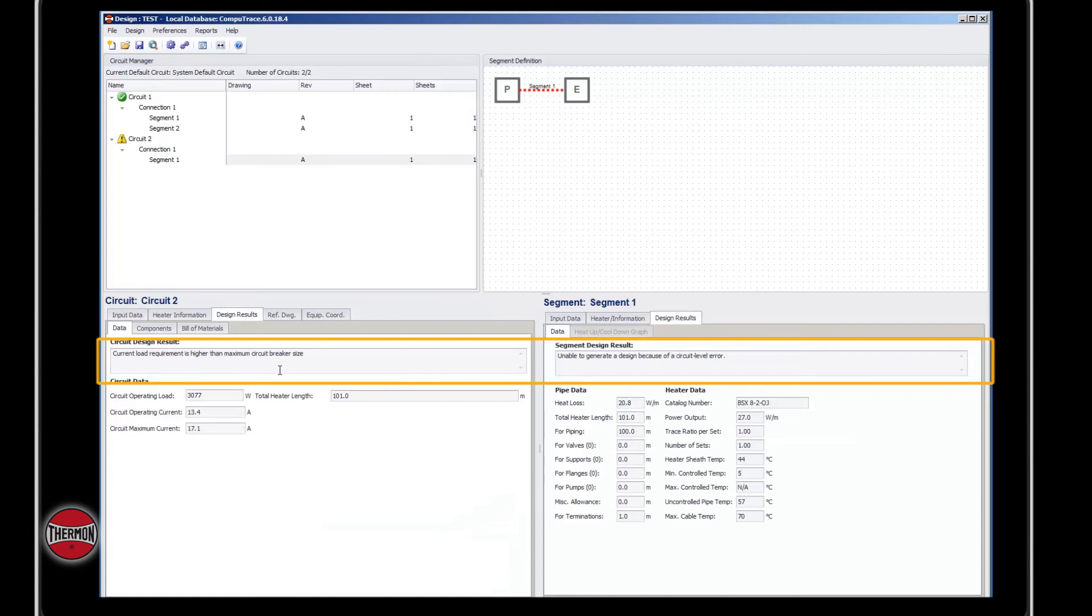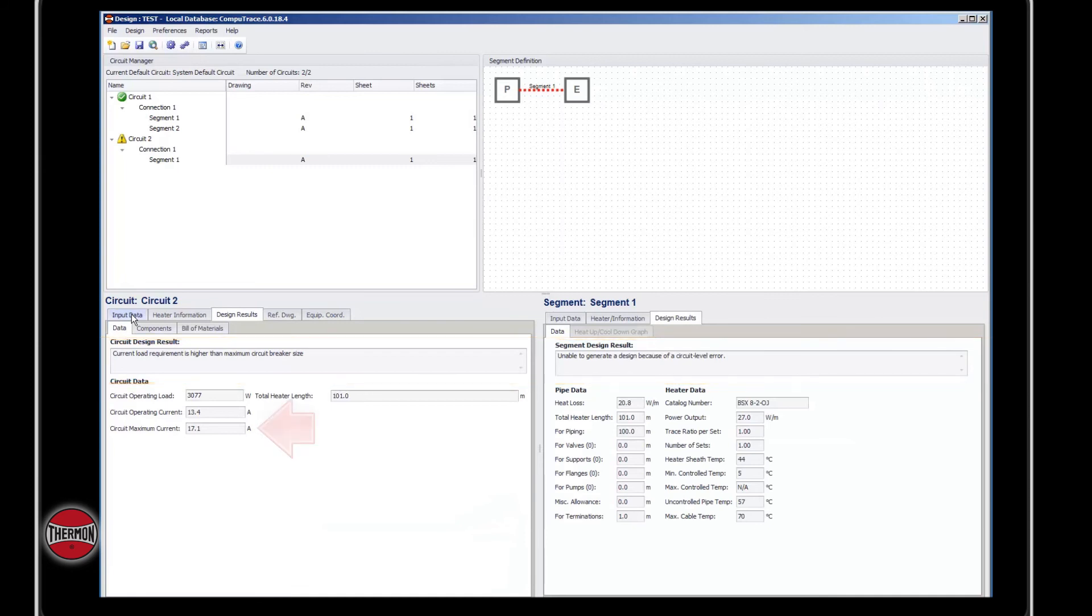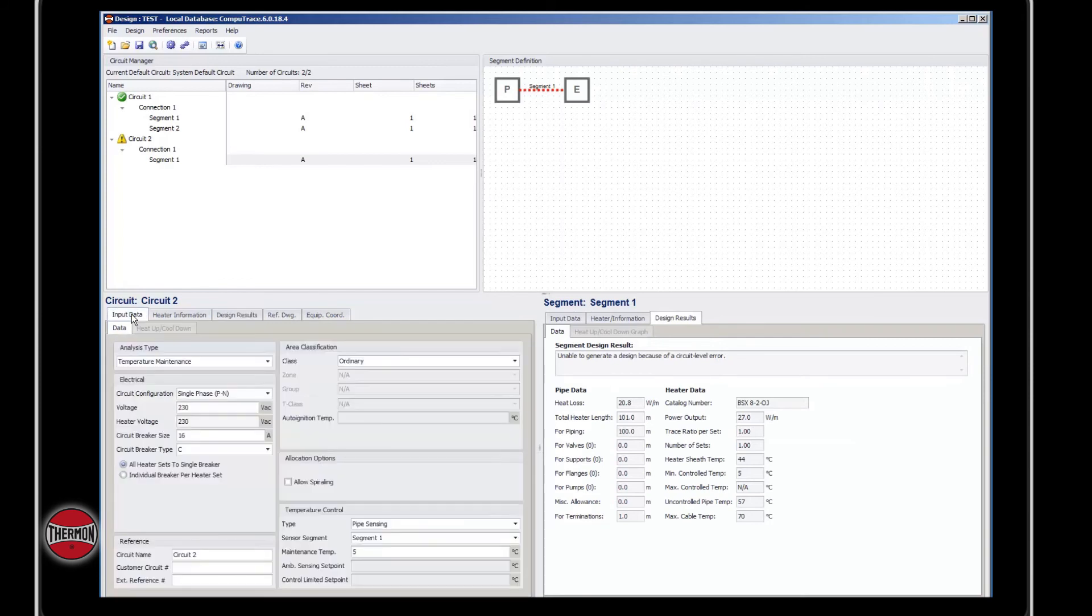You can fix this by going to input data on the circuit level. You'll notice that your circuit maximum current is 17.1 amps. When you go up to input data, you'll notice that your circuit breaker size is 16 amps. Change this to 25 amps.